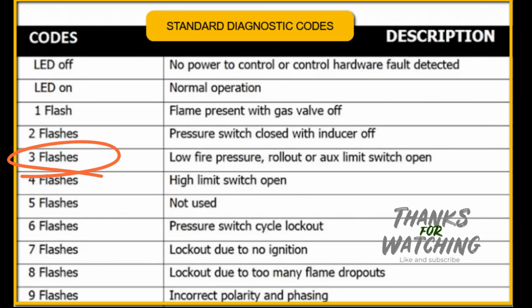If you see this code, it is something on the 24-volt safety circuit. You will have to go through the safety features and test them. We have videos to show you how to check for voltage and ohms. If the high limit switch is open, then your first and easiest thing to check is the furnace filter. If this is dirty, change it and restart. If this is not it, check all the supply and return registers are fully open.